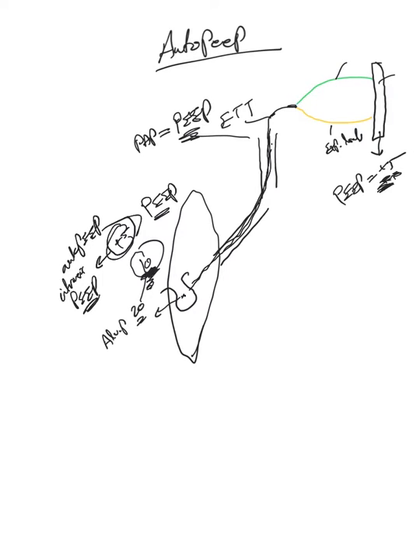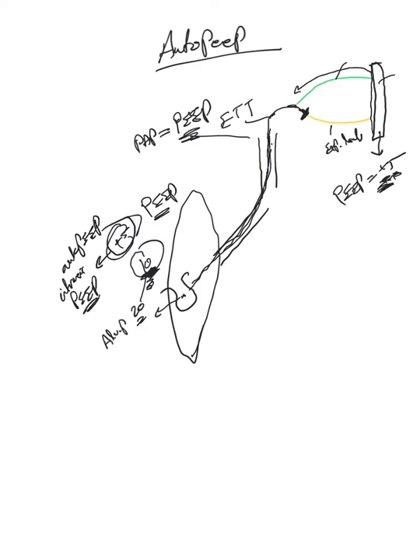So, if the expiration terminated, simply, at the end of expiration, we close this valve. And right before this gives any pressure, positive pressure to stop the flow in, because simply, the flow will continue. And remember, the reason at the end of expiration we stop this, because if we don't close this valve, the air will keep flowing because still there is a pressure gradient.